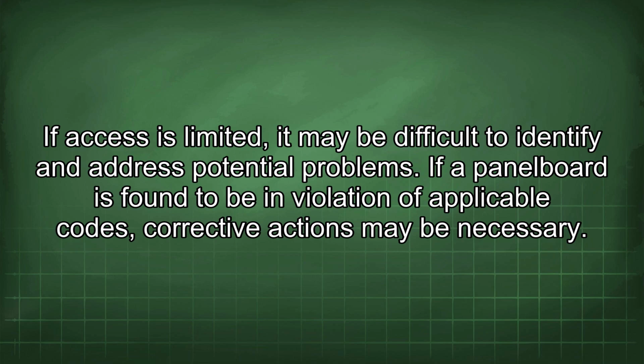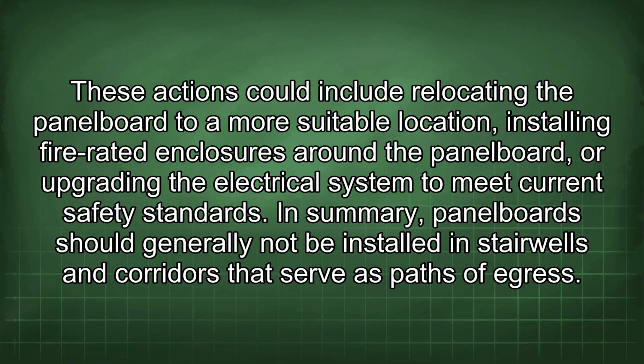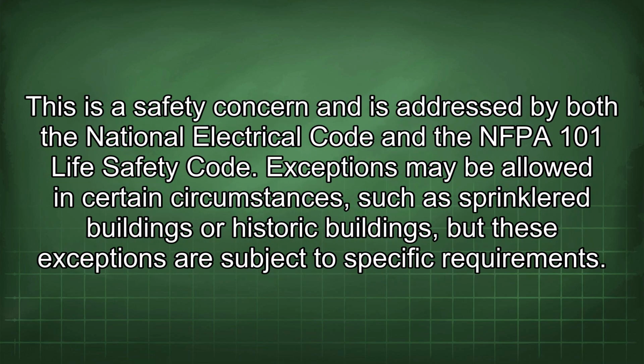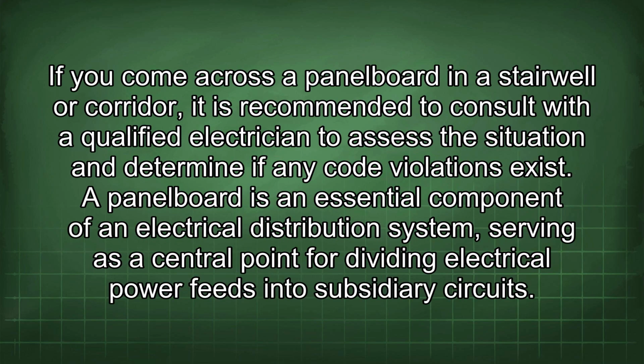If a panelboard is found to be in violation of applicable codes, corrective actions may be necessary. These actions could include relocating the panelboard to a more suitable location, installing fire-rated enclosures around the panelboard, or upgrading the electrical system to meet current safety standards. In summary, panelboards should generally not be installed in stairwells and corridors that serve as paths of egress. This is a safety concern and is addressed by both the National Electrical Code and the NFPA 101 Life Safety Code. Exceptions may be allowed in certain circumstances, such as sprinklered buildings or historic buildings, but these exceptions are subject to specific requirements. If you come across a panelboard in a stairwell or corridor, it is recommended to consult with a qualified electrician to assess the situation and determine if any code violations exist.